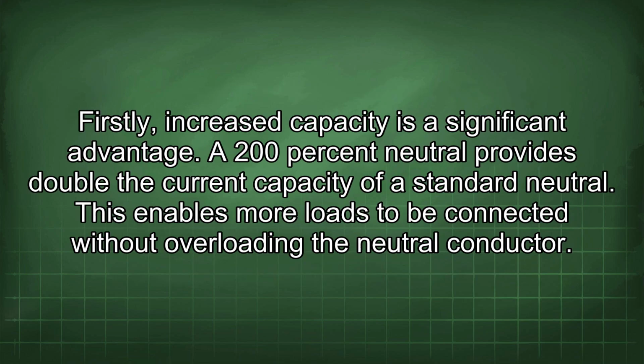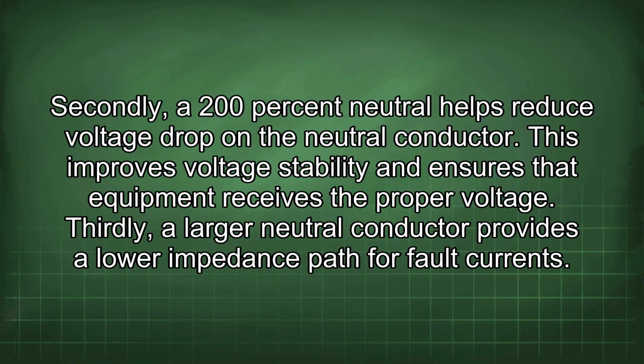Firstly, increased capacity is a significant advantage. A 200% neutral provides double the current capacity of a standard neutral. This enables more loads to be connected without overloading the neutral conductor. Secondly, a 200% neutral helps reduce voltage drop on the neutral conductor. This improves voltage stability and ensures that equipment receives the proper voltage.